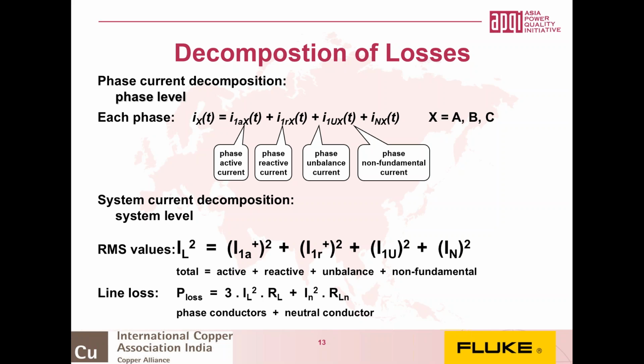The system current is derived from the symmetrical currents, that's the positive, negative, and zero sequence currents, which are also system currents, and combine into a fundamental frequency current phenomenon. Then we only have to use a separate mathematical method for non-fundamental current. If we look at the bottom of the screen, we see the system currents. Beware that this current IL is not a physical current but a mathematical shortcut. It allows us to calculate the effect of the individual phase currents. Once we've calculated this system current IL, calculating the total power loss caused by the phase currents is straightforward. The loss is equivalent to 3 times IL squared times the resistive load.